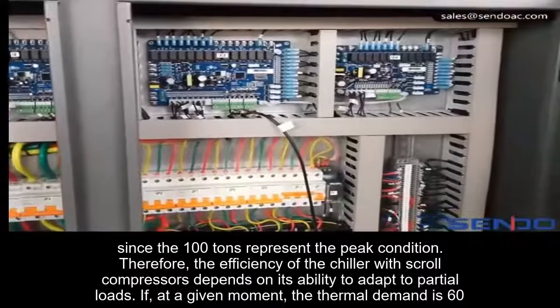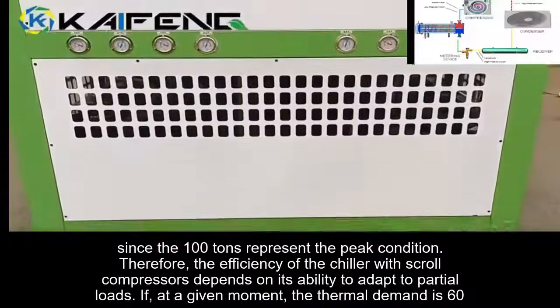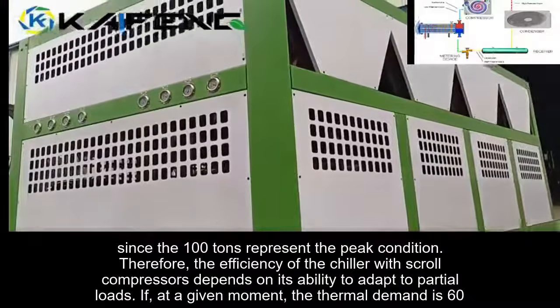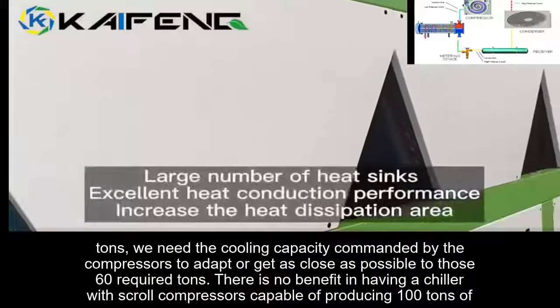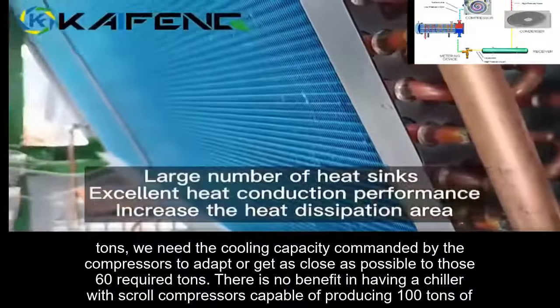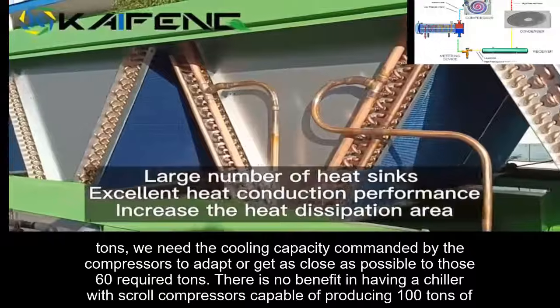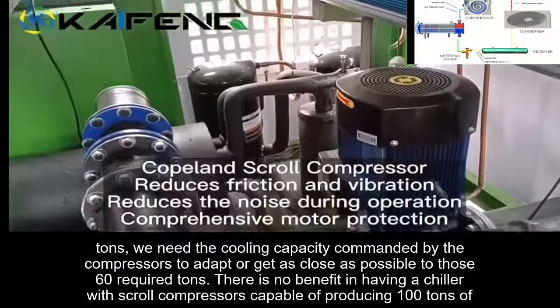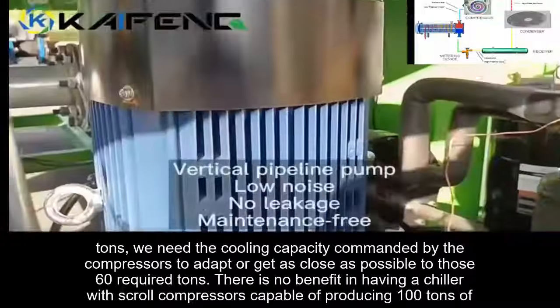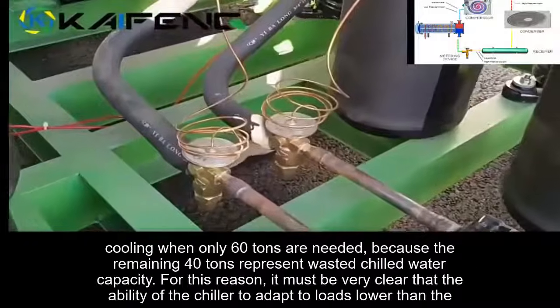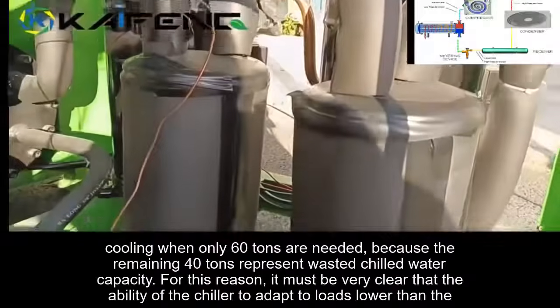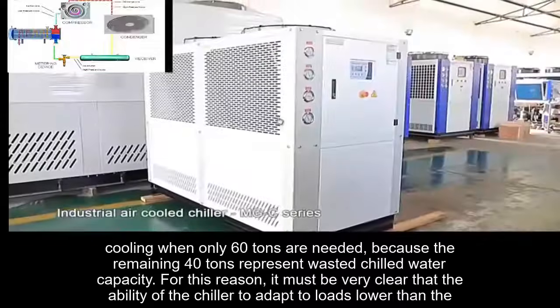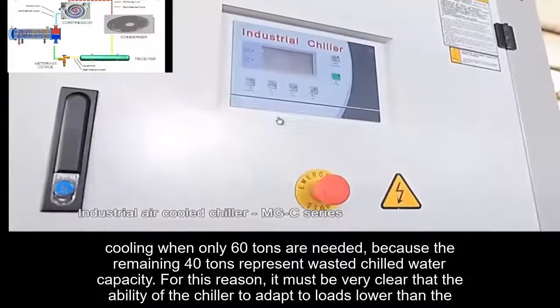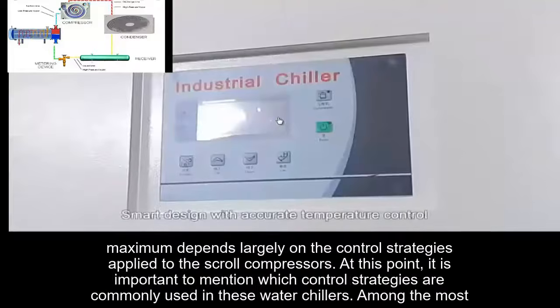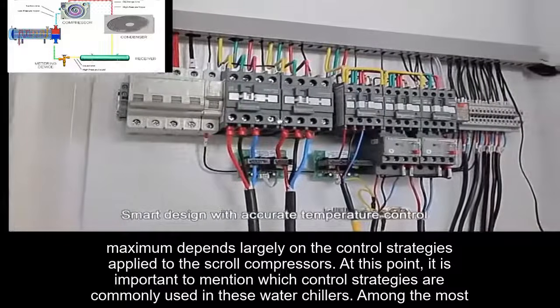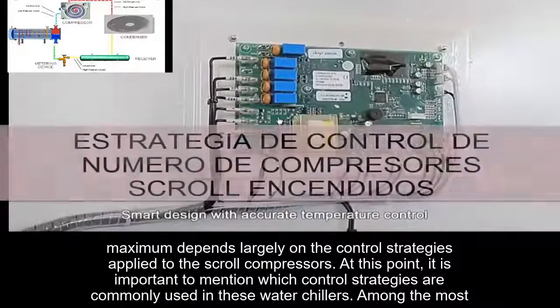represent the peak condition. Therefore, the efficiency of the chiller with scroll compressors depends on its ability to adapt to partial loads. If at a given moment the thermal demand is 60 tons, we need the cooling capacity commanded by the compressors to adapt or get as close as possible to those 60 required tons. There is no benefit in having a chiller with scroll compressors capable of producing 100 tons of cooling when only 60 tons are needed, because the remaining 40 tons represent wasted chilled water capacity. For this reason, it must be very clear that the ability of the chiller to adapt to loads lower than the maximum depends largely on the control strategies applied to the scroll compressors.